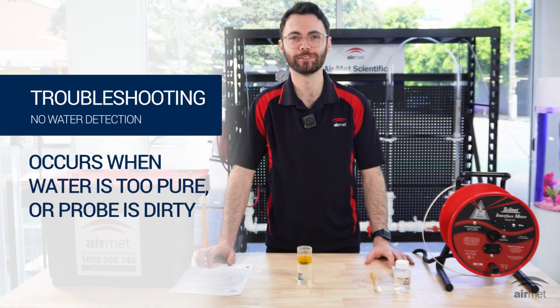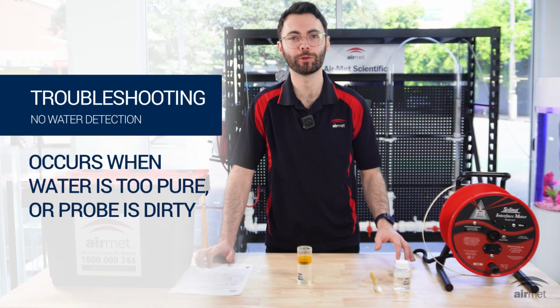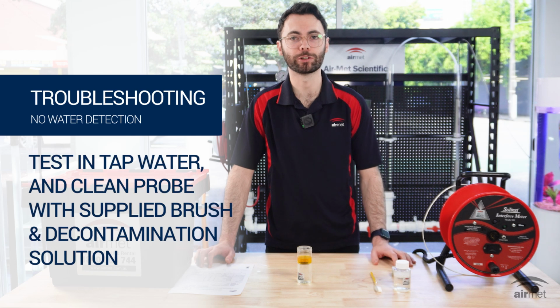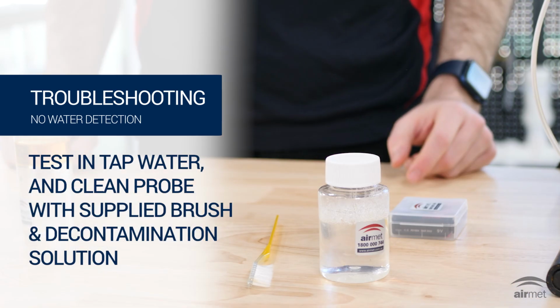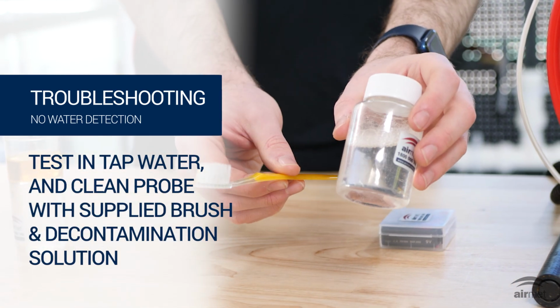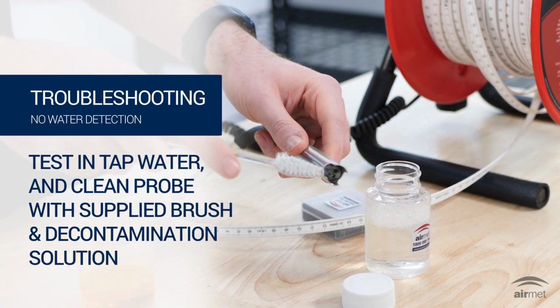No water detection. This can occur when the water is too pure or the probe is dirty. Test in tap water instead of deionized water and use the supplied brush and decontaminant solution to clear away any debris or dirt from the probe.